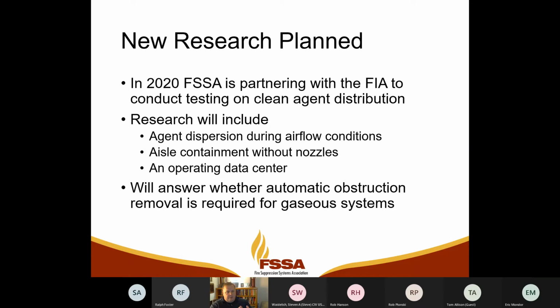Ultimately, we have a data center mock-up built at one of the suppression system manufacturers. It's pretty neat research. We have 3 different makeups of the data center that we can arrange it in. We have a few donated used CRAC units that we're using to help blow air around the space. We've got a bunch of concentration meters that we're setting up, and we're arranging the suppression systems in different ways. We're doing a lot of testing with total flood CO2, using CO2 as a surrogate gas for FM200, because frankly, it's a lot cheaper. So we're fine tuning things with CO2, and then we have some prove out tests that are part of the research plan where we are actually going to discharge FM200 or Novec or whatever donated gases we're getting.